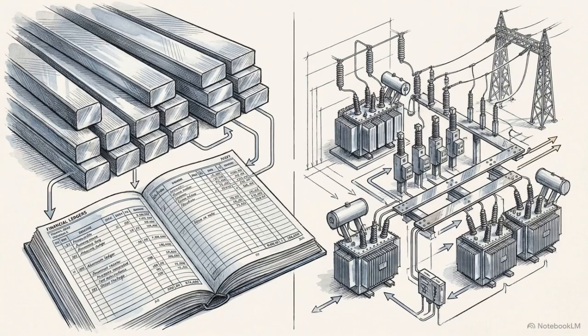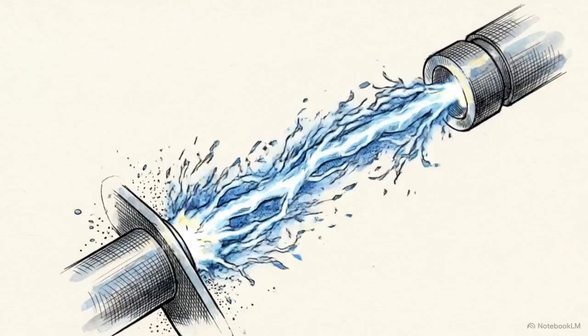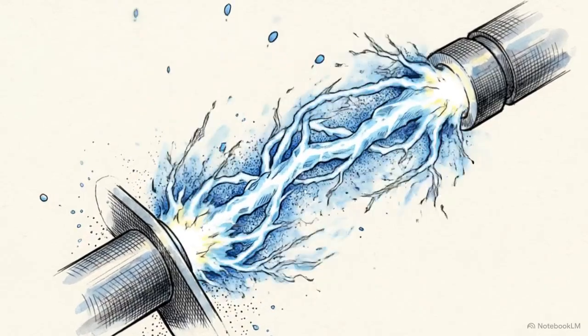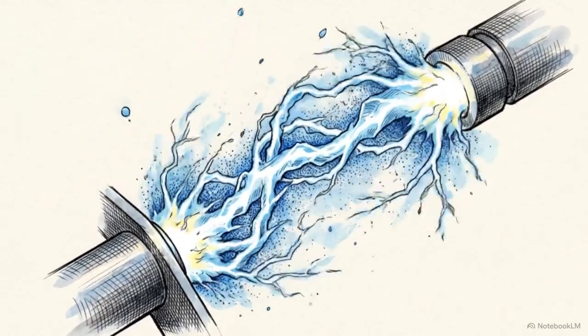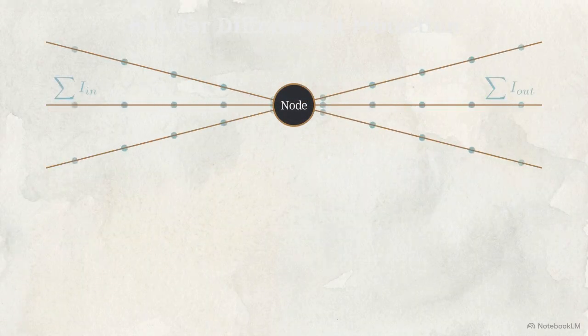Engineering an optimal high-voltage node requires balancing raw physical economics with advanced electrical topology. A brilliant physical topology is useless if a localized fault is not detected and cleared in a matter of milliseconds. This speed is achieved through busbar differential protection, an automated system built on a strict application of Kirchhoff's current law. The logic is elegantly simple.